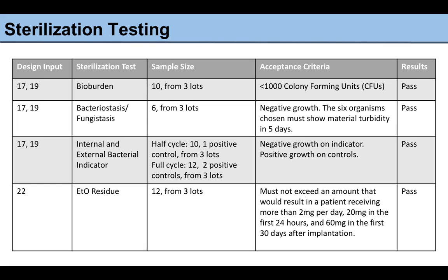And the acceptance criteria for this test was that the amount of ETO left on the device after sterilization must not exceed an amount that would result in the patient receiving more than 2 milligrams of ETO per day, or 20 milligrams in the first 24 hours, or 60 milligrams in the first 30 days after implantation. And this test passed as well.